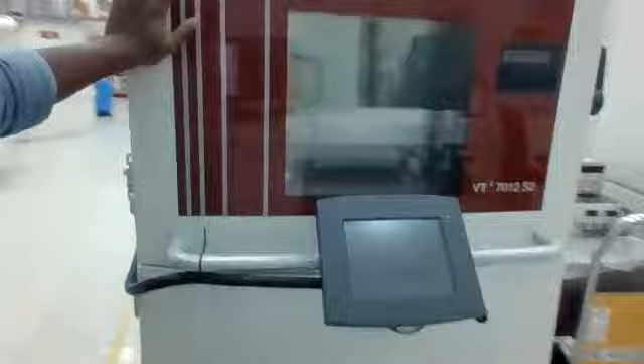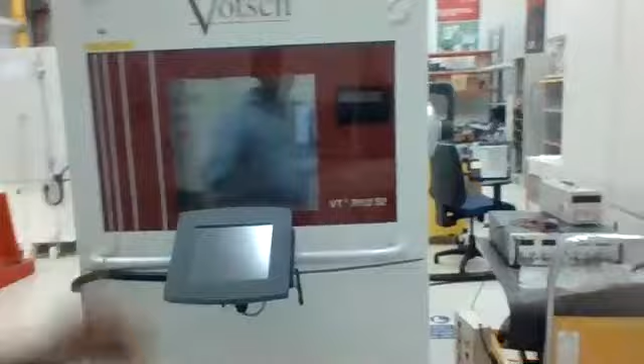What it does is it has a cooling unit at the bottom and a heating unit at the top. If you want to put equipment inside and operate it for 5 minutes in heating mode, then 5 minutes in cooling mode, then again 5 minutes in heating mode, you can do that in this particular test setup. This is not possible in the other chambers, which are dedicated only for heating, but this chamber can do both heating and cooling.